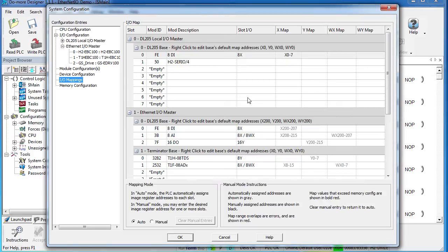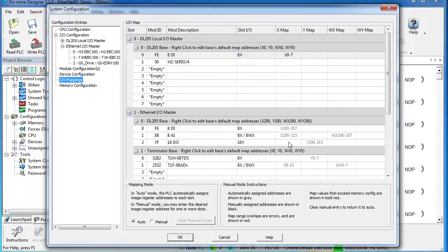That does two things. One, I can now install as many modules here as I want, and as it automatically assigns the addresses, it won't impact the addressing on my slave devices. And the other thing I kind of like about this is it puts each slave on a different addressing boundary—it just helps me keep track of which I.O.s go to which slave device.